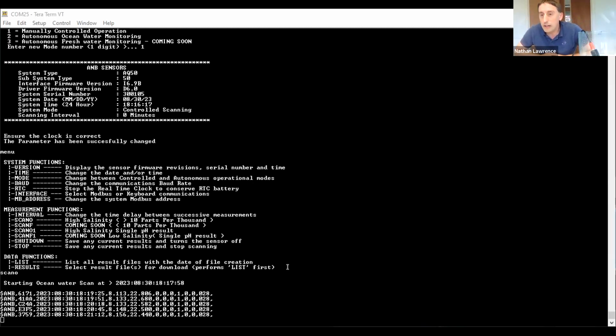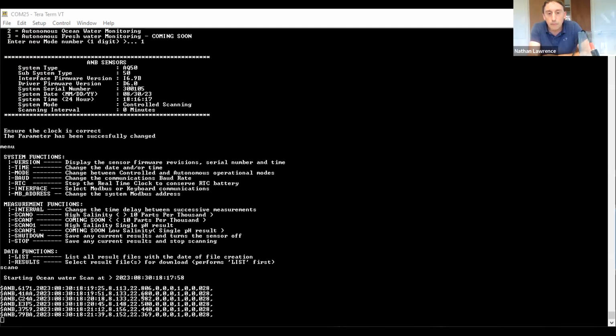Periodically, it will do a reference electrode check because this is how we stay calibration free, as we said earlier. The output of the sensor is shown here. We've got the date and the time. We've got the pH of the solution. We've got the temperature delivered in degrees C, and we have a range of other outputs here.